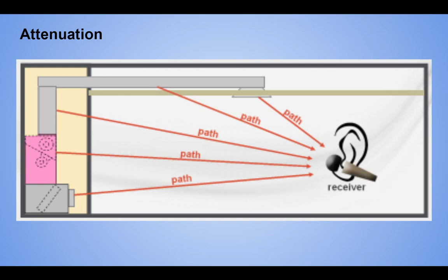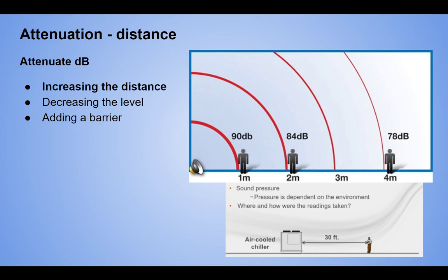We also have our go-to standard with the five paths. This one would be return air. This would be casing. This would be supply side. Remember, this is sound isolation here. Once we get in here, now we're talking about mechanical noise control or background noise. But all five of these figure into the NC curve. If we have this set at the level that we want and work through that, and this is good, but we have not addressed the isolation, then our NC still fails. Our noise criteria, our background noise still fails. So we've got to do both. And we've got to take care of all of this before we do any architectural acoustics aspects. So the trump card that we have is increasing distance. And picking up on this last, this is the best aspect.